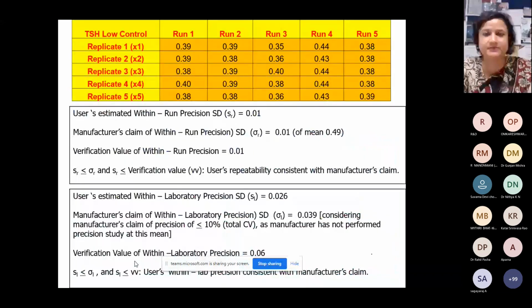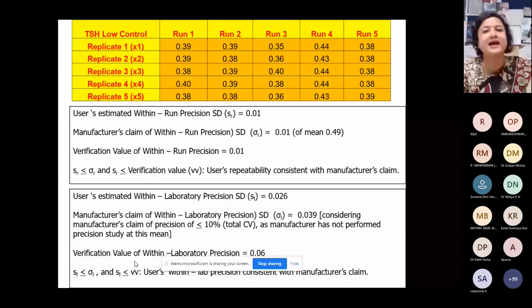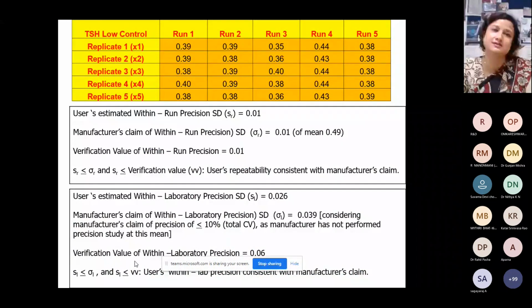So the current guideline is 5 runs for 5 days, so a total of 25 replicates. Today you start the run of the low control and high control, at least a minimum of 2 levels of control. And if you can, do 3 levels of control in the immunoassay parameter, with 5 runs today, then tomorrow 5 runs, and so on for 5 days, so 25 replicates.